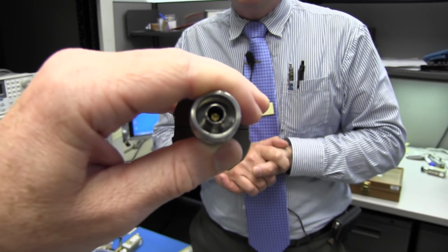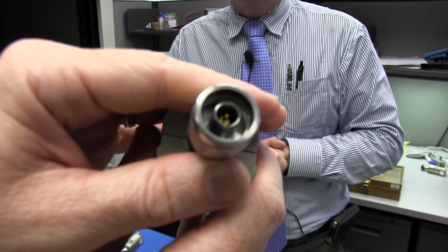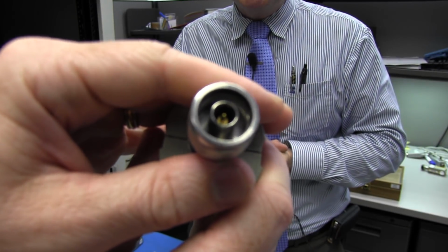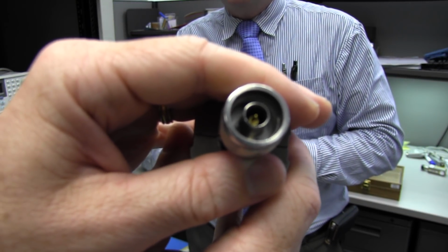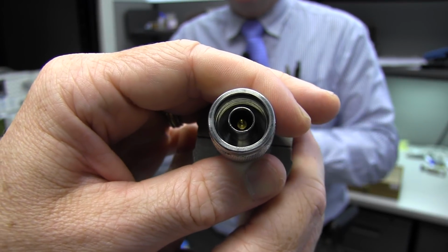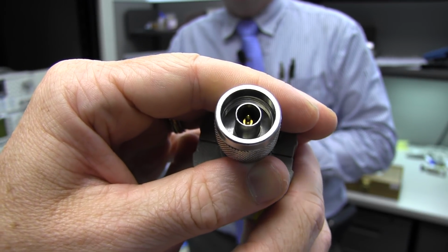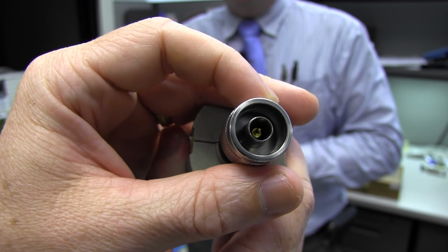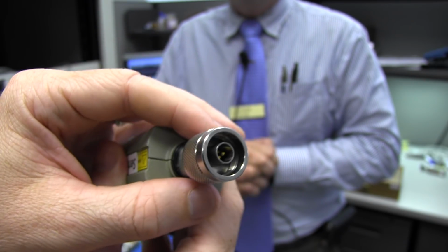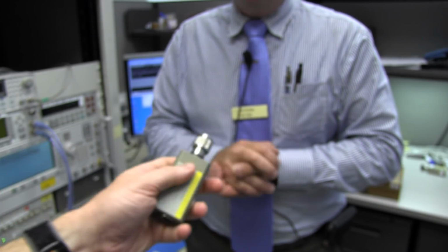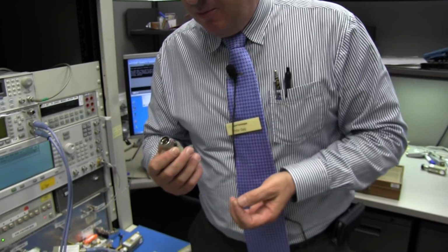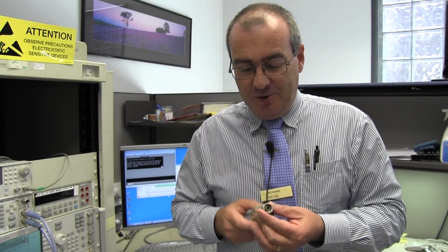Now most of the N-type connectors out there are production grade or less. Often you'll see an N-type connector and it's got a sharp point on the end of it, like a taper. If you're working with precision equipment and you buy a $20 connector saver that's got that tapered pointy bit on it, you're actually going to cost yourself a lot of money, because you put that less precision connector onto your metrology grade connector, and you're going to blow it away.